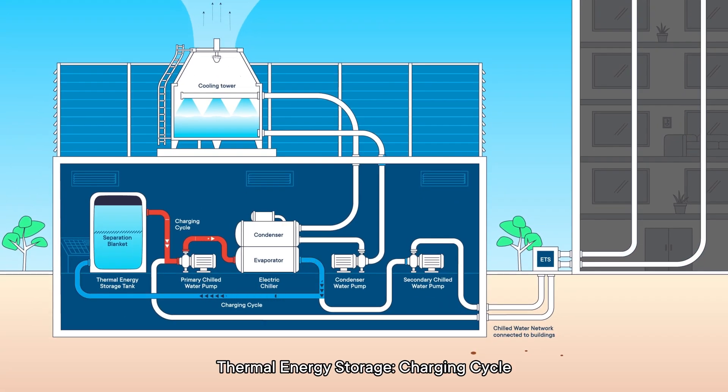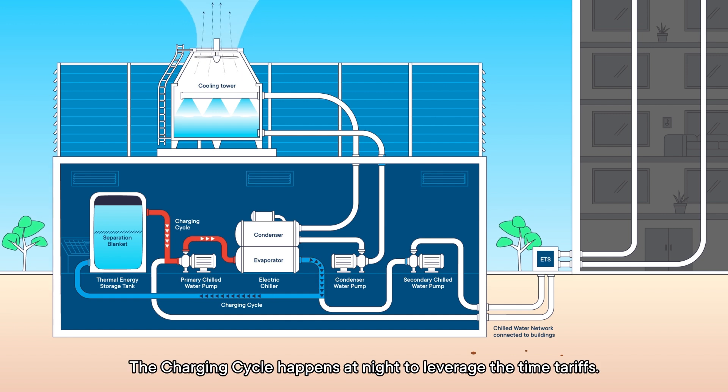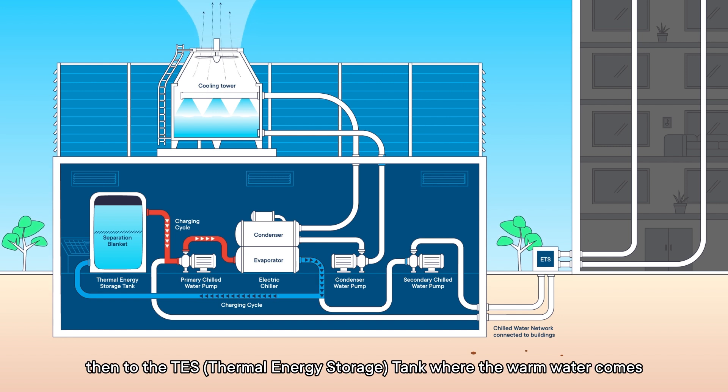Thermal energy storage charging cycle: The charging cycle happens at night to leverage the time tariffs. The TES tank is charged using the chillers, then to the TES tank where the warm water comes from the top and back into the chiller.